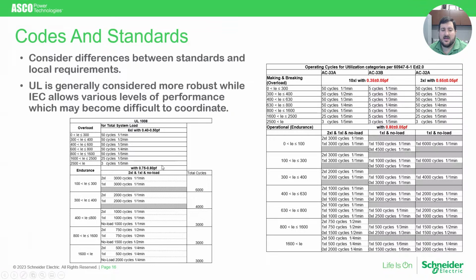UL 1008 only really has two rating levels, but primarily everyone in the market only qualifies to the more advanced rating level for emergency standby systems, which is outlined here, and is in line with the more strenuous level of testing that you see for AC33A here. So overall, the UL standard is more closely aligned with the most stringent level of the IEC certification, leading to that conclusion.